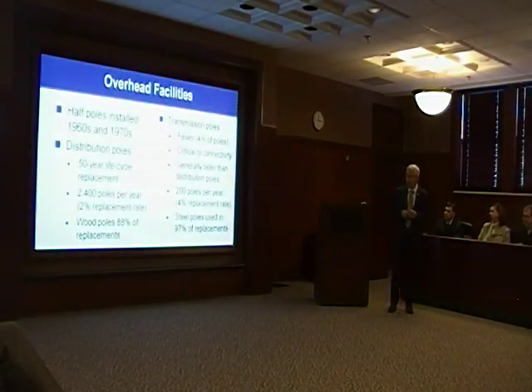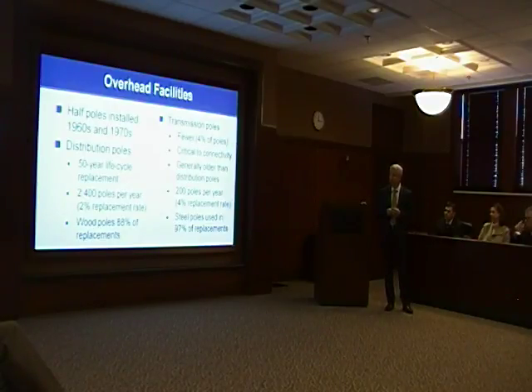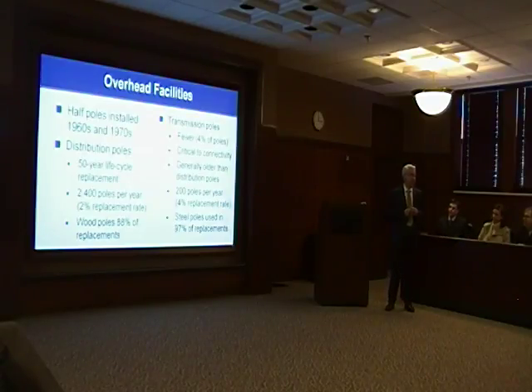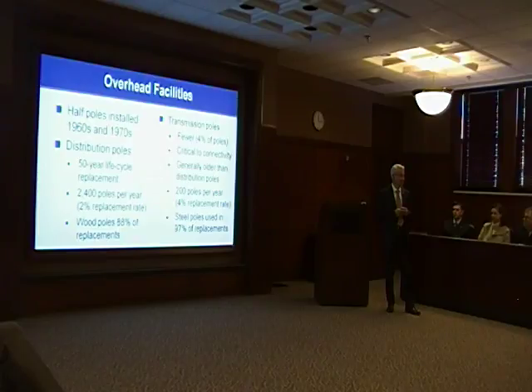Moving over to the overhead facilities - as I mentioned, we have transmission overhead and distribution overhead. Most of our poles were put in during the 60s and 70s. Distribution poles typically have a 50-year lifespan. The bread and butter of our system are wooden poles, standard height of 45 feet. We use wood poles mostly because they're readily accessible from the roadway, easy to move around the system and install, and inexpensive at about $250 a pole - not a lot of expense.